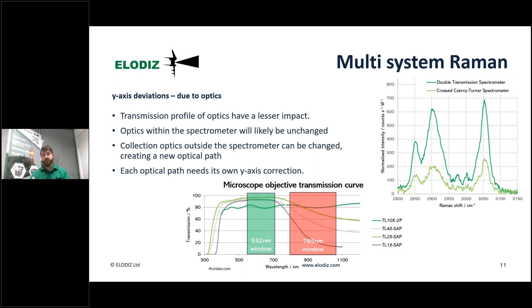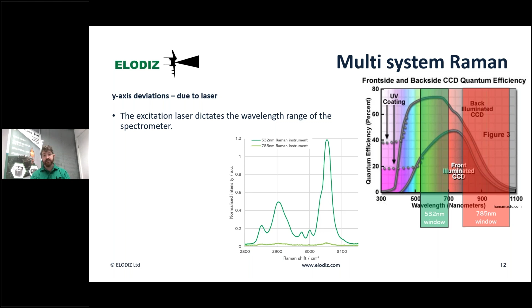And lastly, the big one, the one that most people will know about if they have used 532 and 785, is that there is a vast difference in the intensity of the CH bands in that region. Again, we're looking at a 785 spectrometer and a 532 spectrometer. These are both the same model of spectrometer, but they have slightly different grating positions, etc., to allow them to be 785 or 532. And you can see that there is a large difference between the intensity that you're seeing in that region.